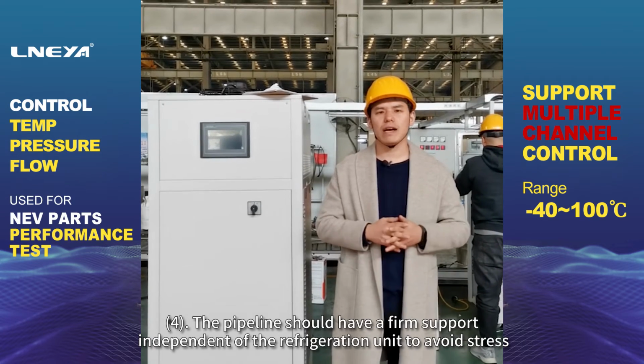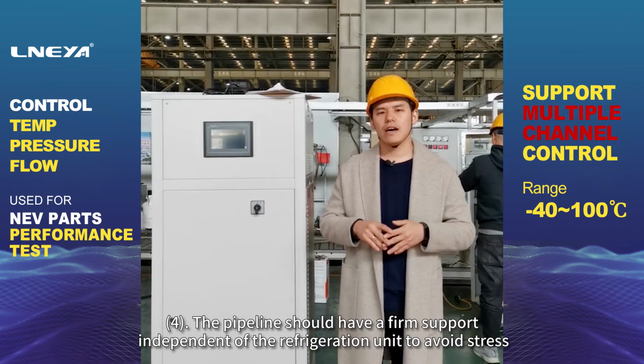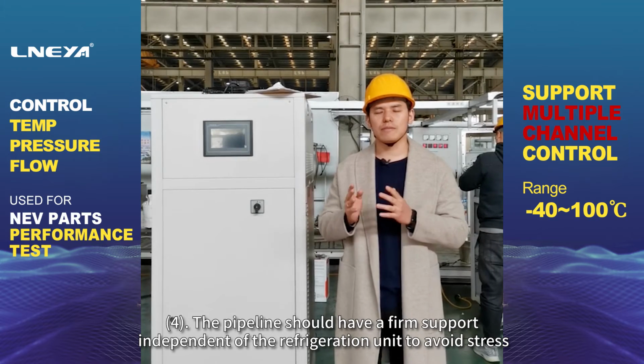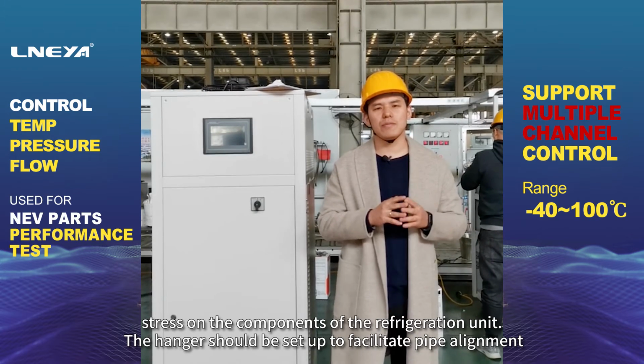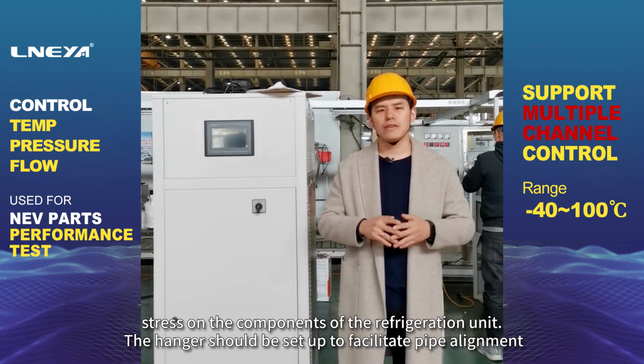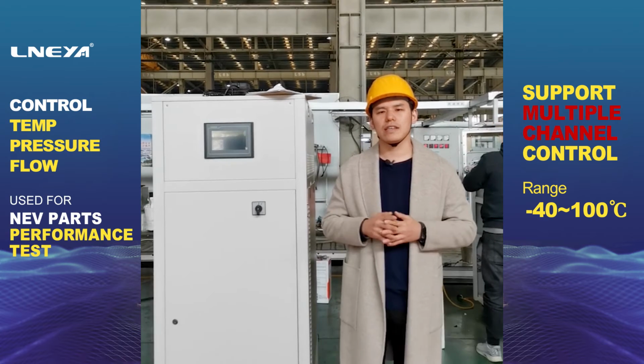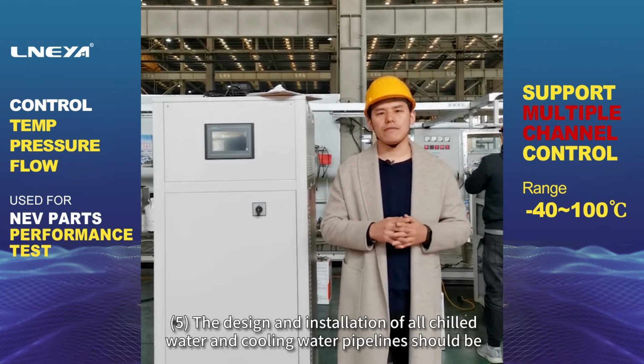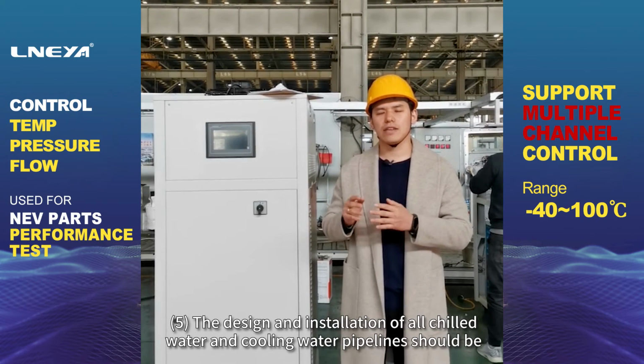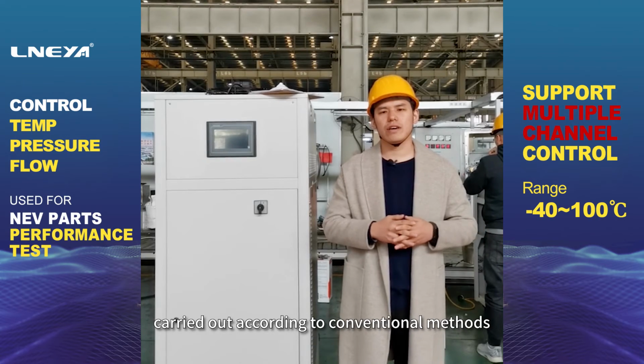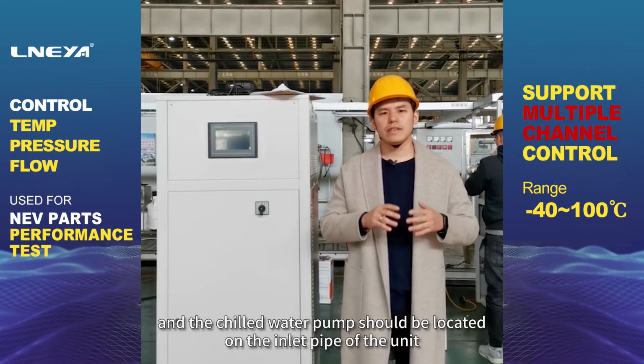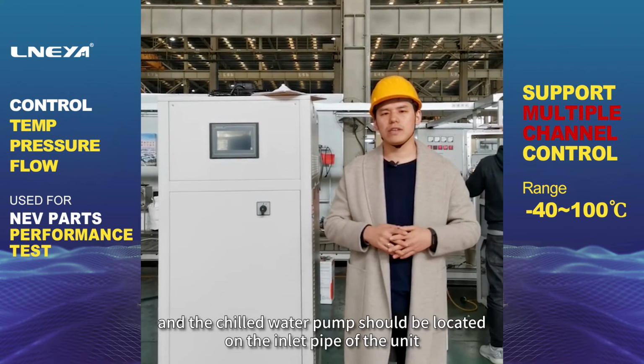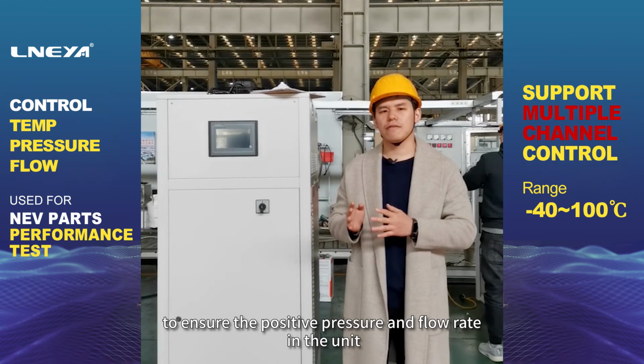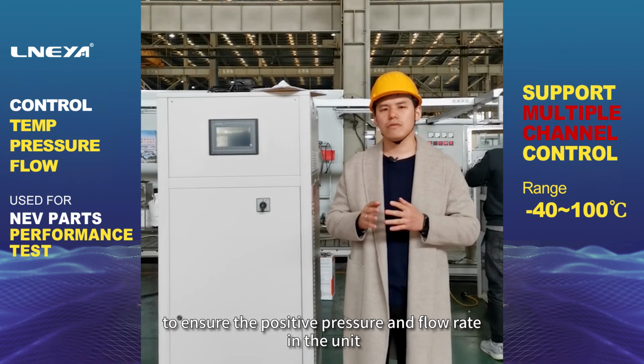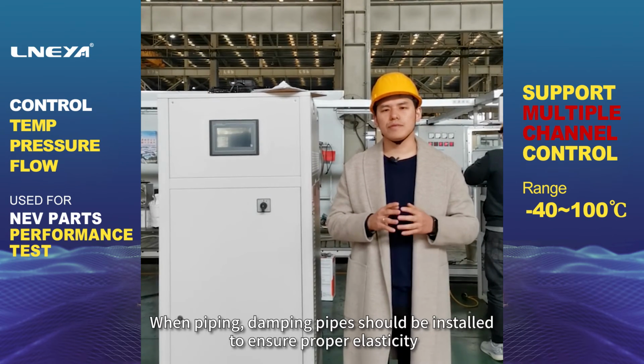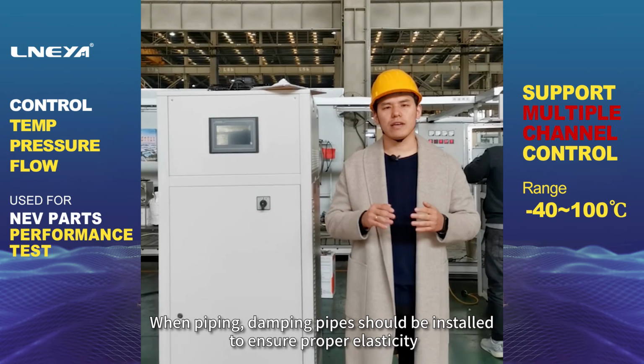4. The pipeline should have a firm support independent of the refrigeration unit to avoid stress on the components of the refrigeration unit. The hanger should be set up to facilitate pipe alignment. 5. The design and installation of all chilled water and cooling water pipelines should be carried out according to conventional methods, and the chilled water pump should be located on the inlet pipe of the unit to ensure the positive pressure and flow rate in the unit. When piping, damping pipes should be installed to ensure proper elasticity.